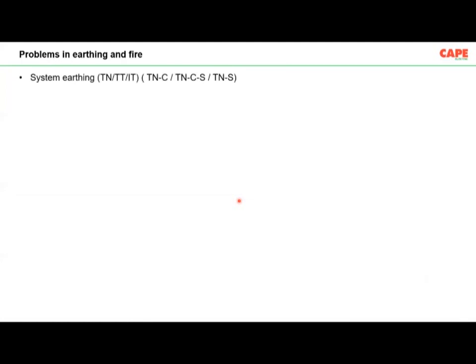Now, what are the problems? When it comes to earthing, the following problems we are facing, wherever we go for an audit. Number one, what kind of system earthing you are using? Normally, it is unknown. Are you using TN or TT or IT? Mostly the engineers, not all the engineers, but most of the engineers don't know. Then we have to explain to them. Then they say, okay, it is a TT system, but sometimes it is not a TT system. It is a different kind of system. So the information on system earthing is missing. Protective earthing, like connecting the steel pipe, firefighting pipe to your equipotential bonding conductor in a high-rise building, mostly it's missing. People don't do this.